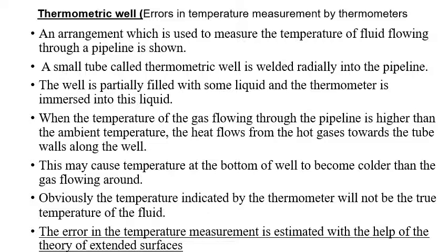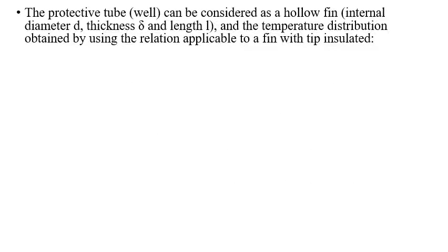The error in the temperature measurement is estimated with the help of the theory of extended surface. So using the fin concept, we find what is the error that is happening. The protective tube well is considered a hollow fin with internal diameter d, thickness delta, and length L, and the temperature distribution is obtained using the relation applicable to a fin.